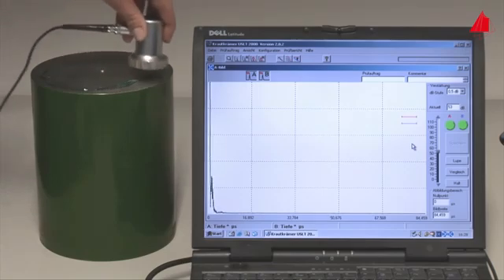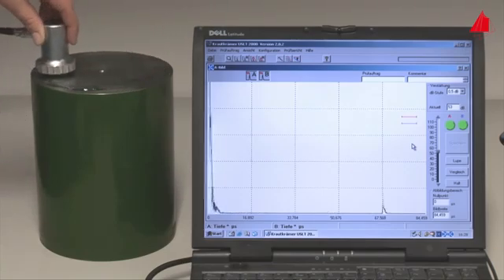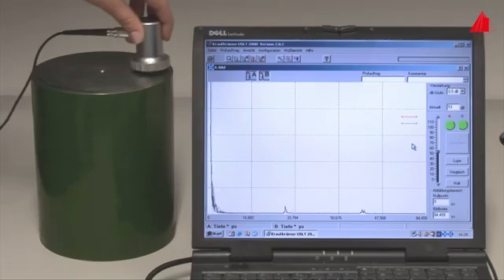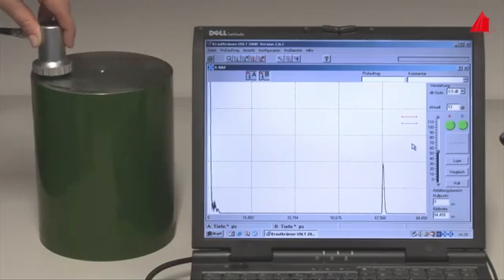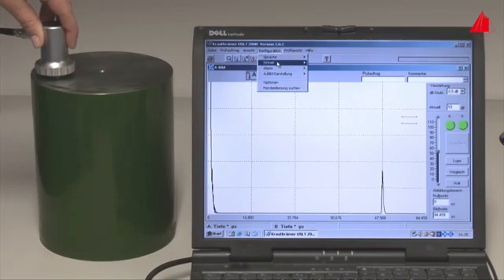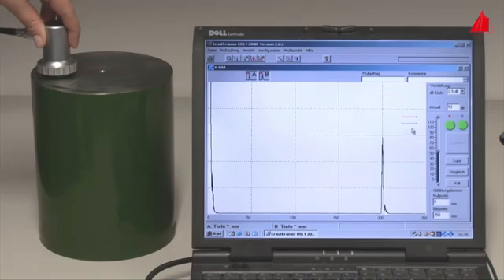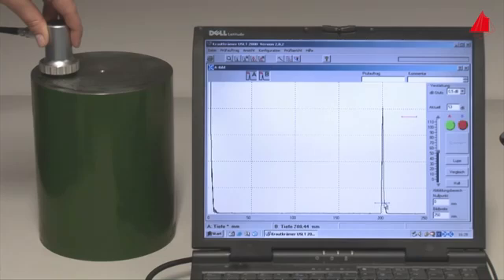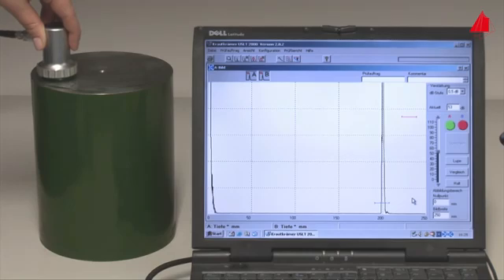The material tester spreads out the gel evenly on the top surface so that she is able to examine the entire cylinder. Using the velocity of sound in the material, one can plot the calculated depth on the monitor to the right instead of time—a very useful feature. With the help of so-called trigger gates, which may be set on the echoes with the computer mouse, the depth of the defects can easily be read off at the lower left hand corner of the monitor.